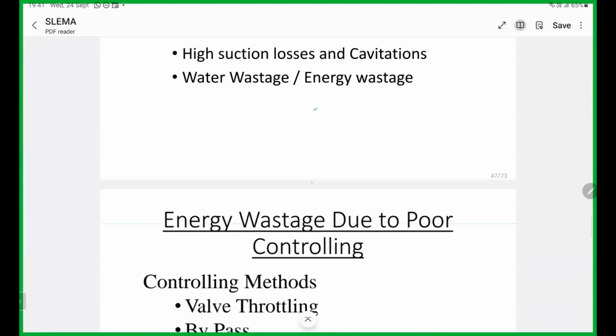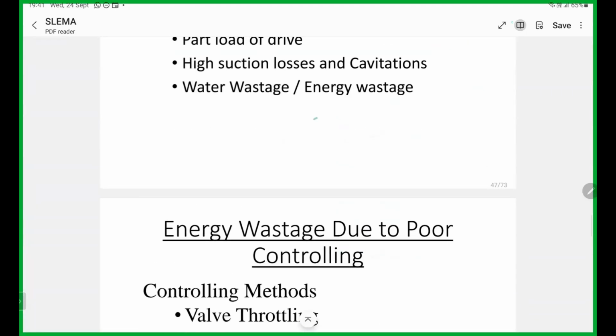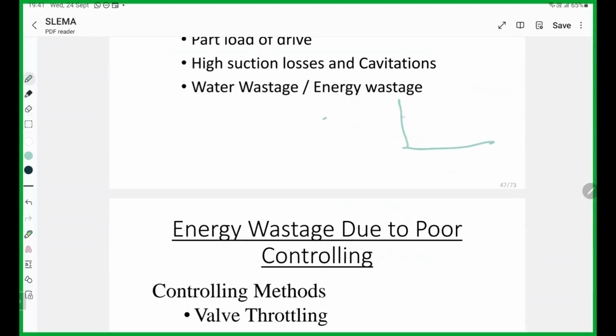Then another one is that most people forget it. For a flat system curve, the best way to control is parallel pumping: one, two or three pumps. Parallel pumping is the best option. If the system is flat, the parallel pumping duty point and the single pumping duty point are almost the same, so the single pump efficiency is not going to change, right? So for a flat system curve, parallel pumping is ideal.